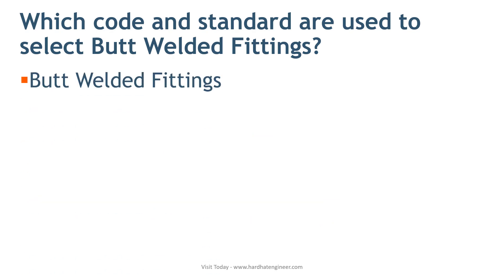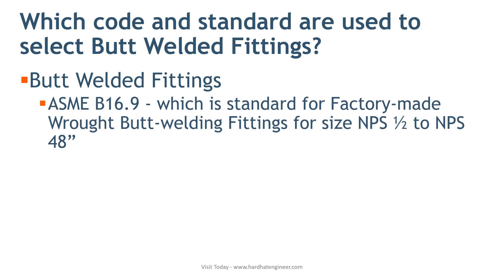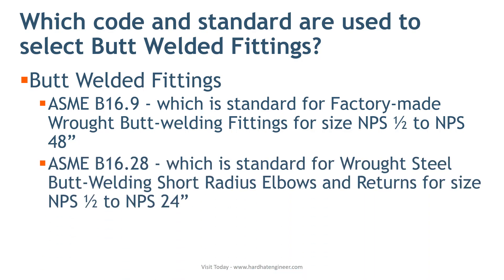Butt welded fittings, also known as wrought products: dimensions and list of materials used to manufacture wrought fittings are covered in ASME B16.9, the standard for wrought steel butt welded fittings for sizes NPS 1/2 inch to NPS 48 inch, and ASME B16.28, the standard for wrought steel butt welded short radius elbows and returns for sizes NPS 1/2 inch to NPS 24 inch.